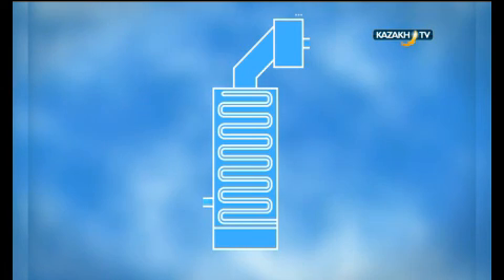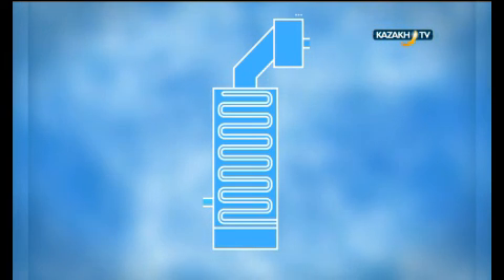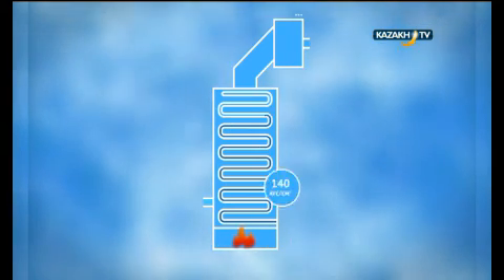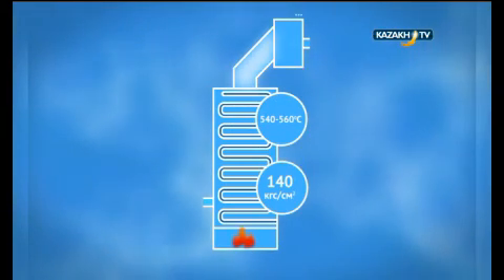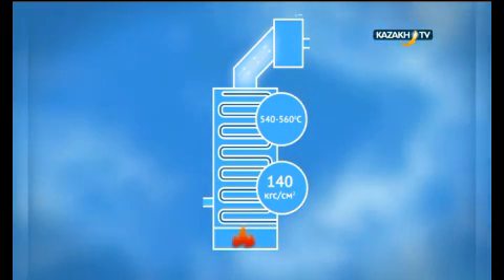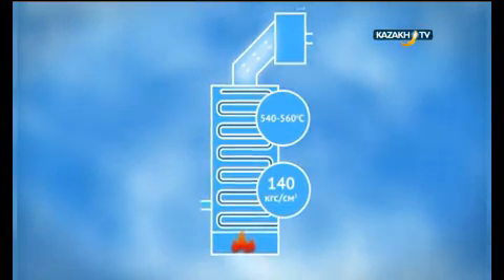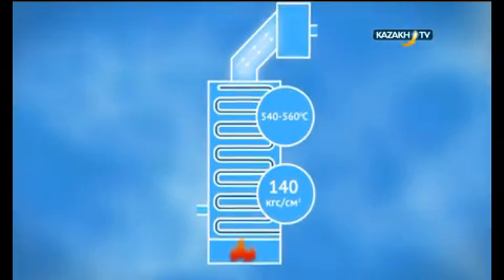The furnace that is set up at the power plant is a rectangular tank, the walls of which are screened with pipes along which water flows. Inside the furnace, coal is burnt, resulting in a flame. The water in the pipes gets hotter under the pressure and partially turns into steam. This steam, under the temperature of 540 to 560 degrees Celsius and under the pressure of 140 kilogram force per square centimeter, is delivered along the pipes to the turbine.